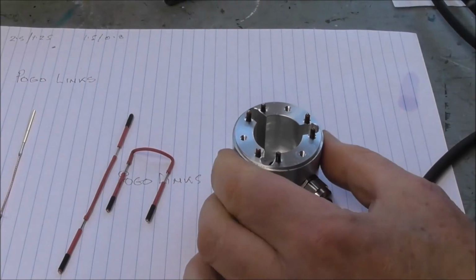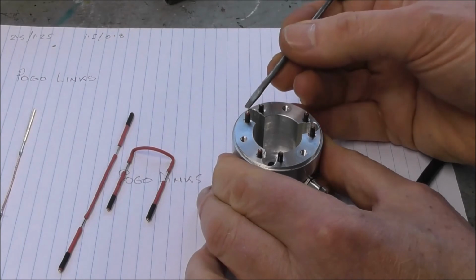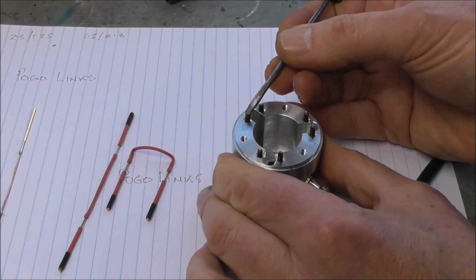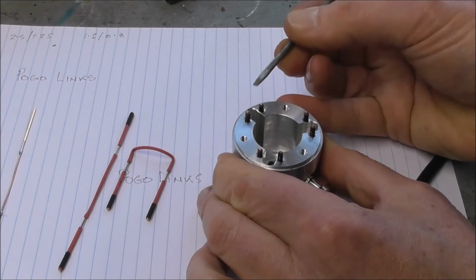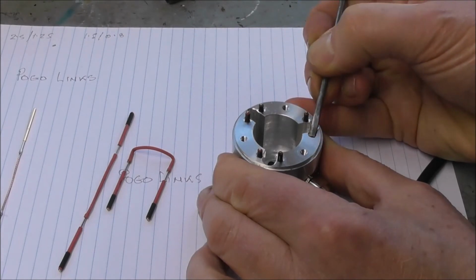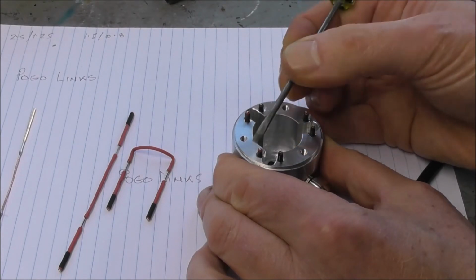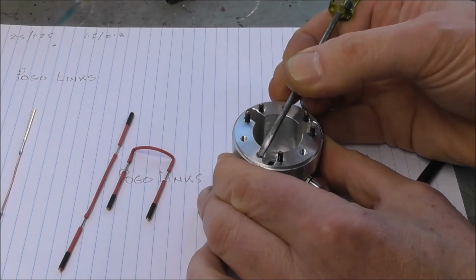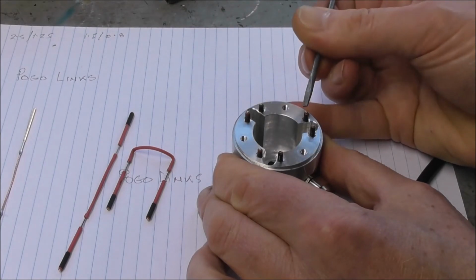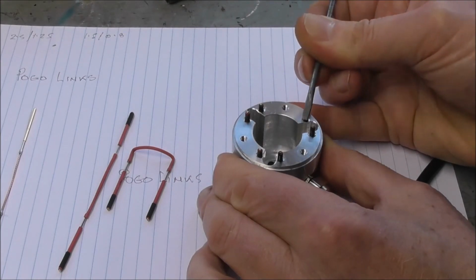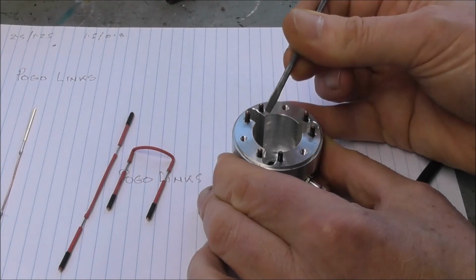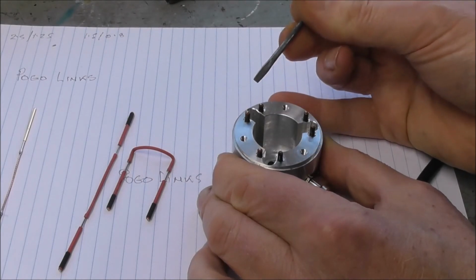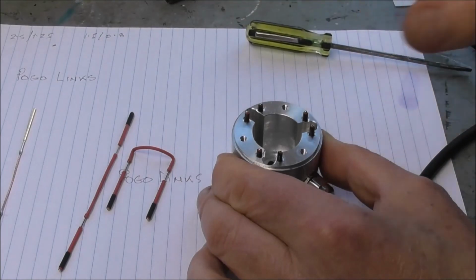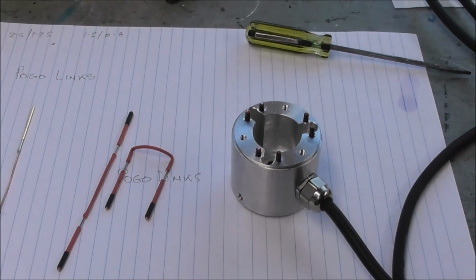So that's it all together now. So just reiterating, it's important that all the pogo pins move up and down freely, and that the little gold contacts on the end are exposed, that there's no insulation over them. And if that isn't operating properly, you could well have problems with the connectivity of the circuit when you put it all together.